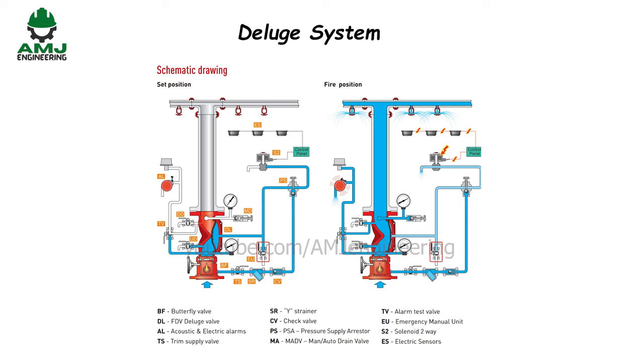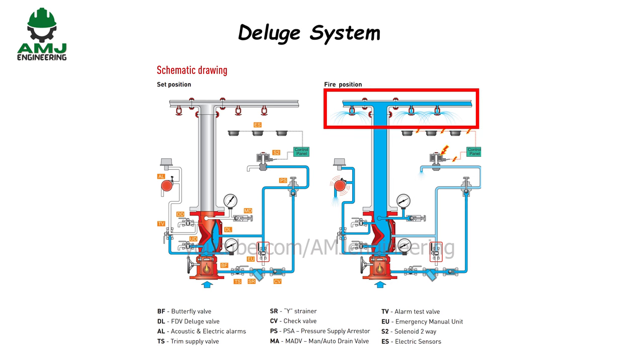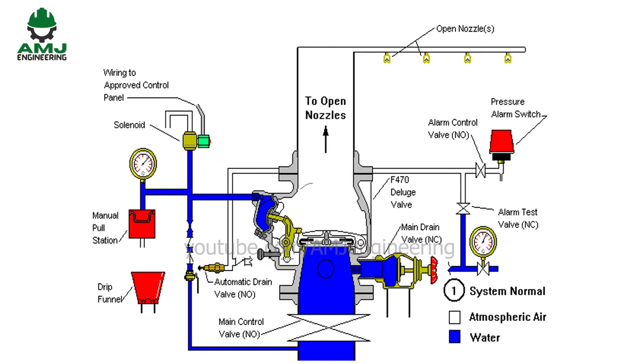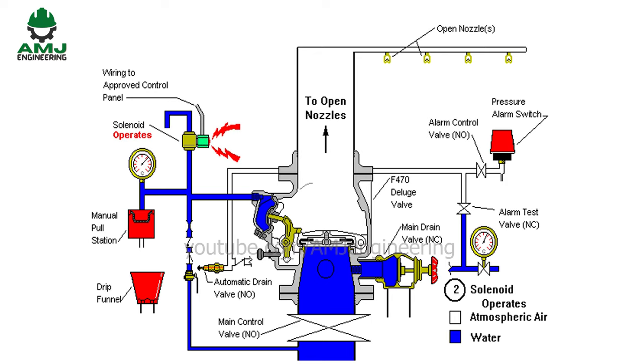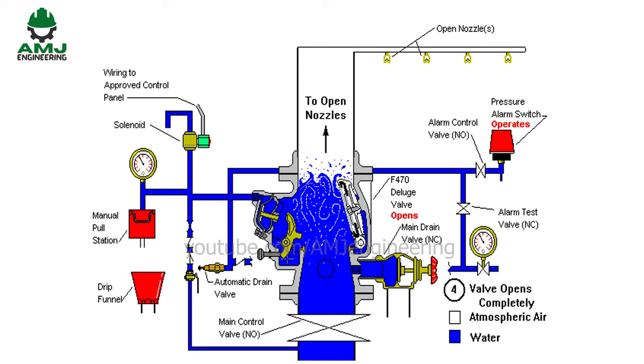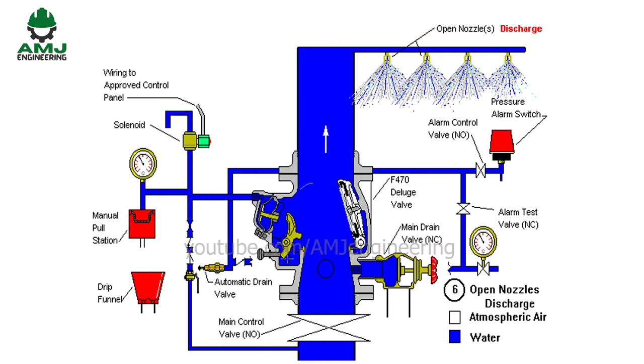Deluge systems are similar to pre-action systems in that they use another type of detection for operation. However, the biggest difference is that deluge systems use open sprinklers or nozzles. Instead of getting water flow from individual heads that have operated, once water fills the system, water will flow from every sprinkler head. A deluge valve will keep water from filling the system until the operation of another detection system, such as smoke detection. Once the detection system is activated, water flows from all open sprinklers or nozzles.